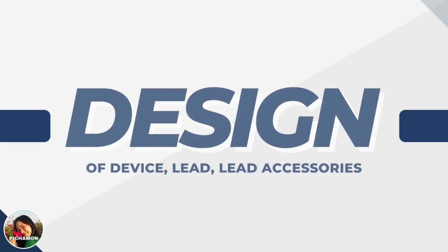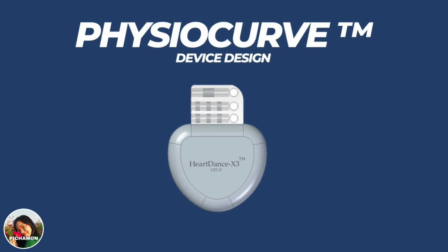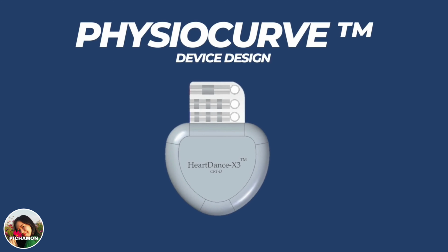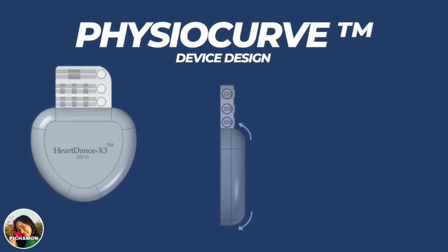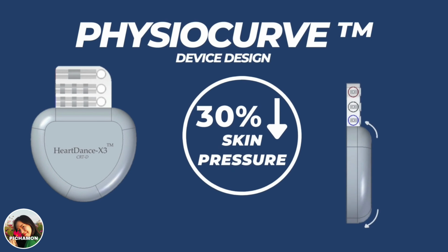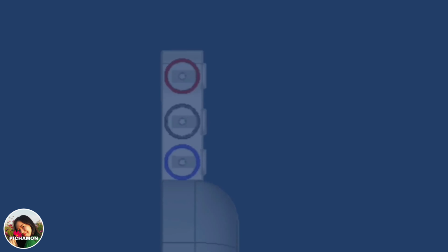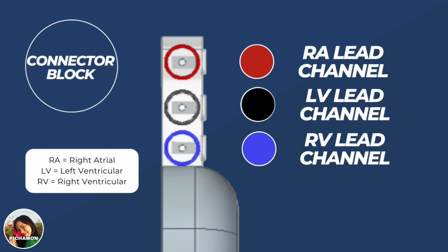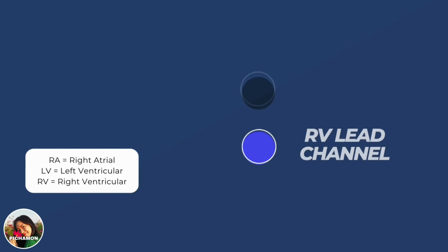Our device appearance is designed from PhysioCurve design, which has the four-part curve and smooth edge of the device in the connector header and bottom. It can reduce 30% of skin pressure and enhance the patient to be more comfortable. The connector block also labels the channel of lead insertion by color to avoid the mistake of lead insertion.